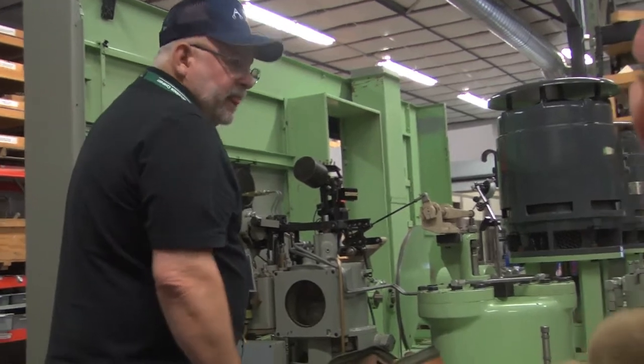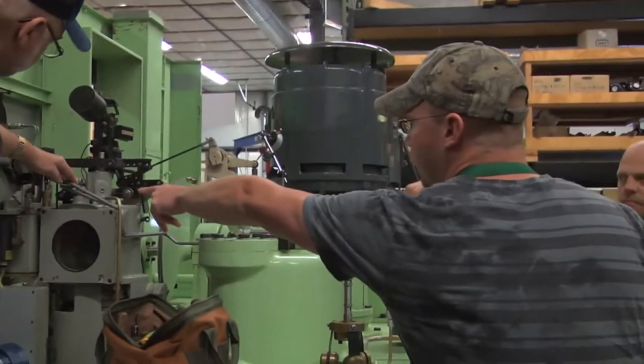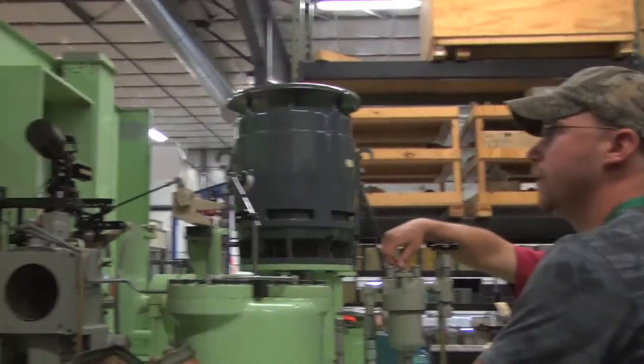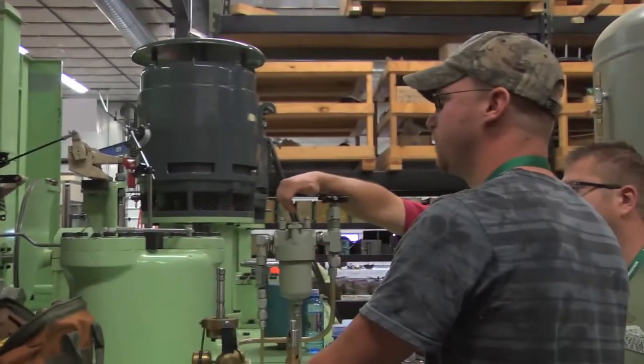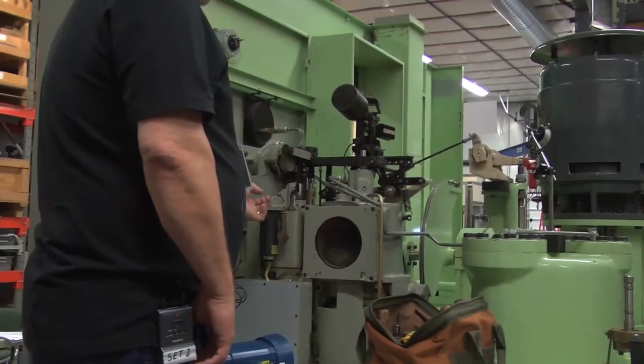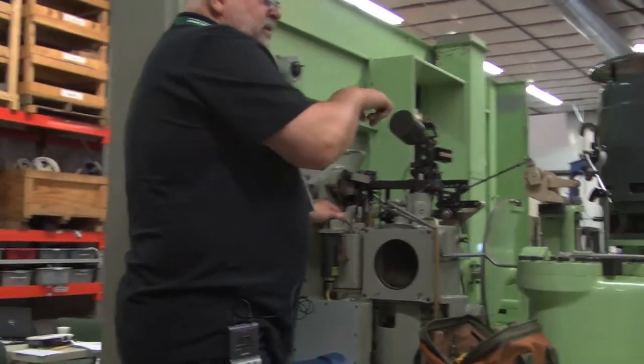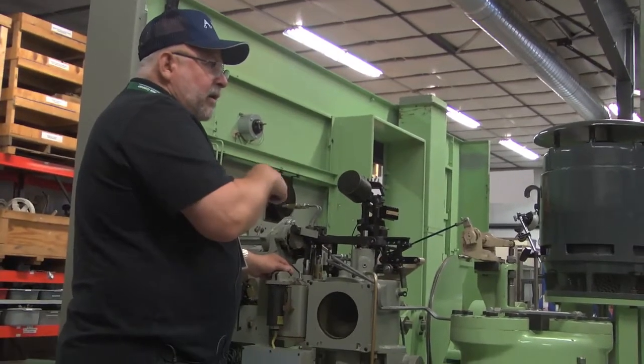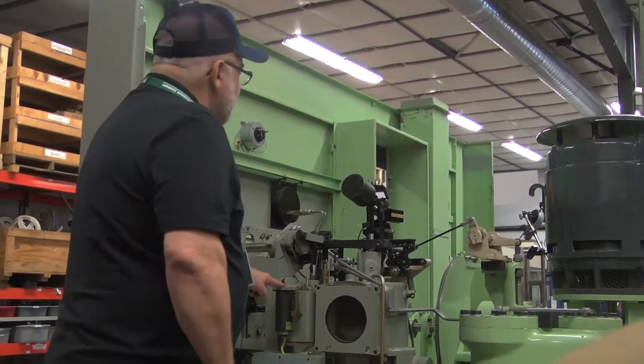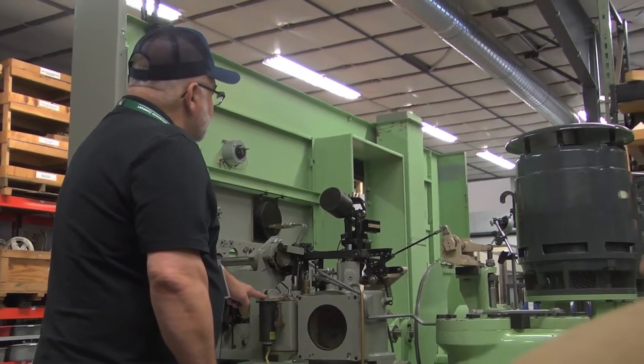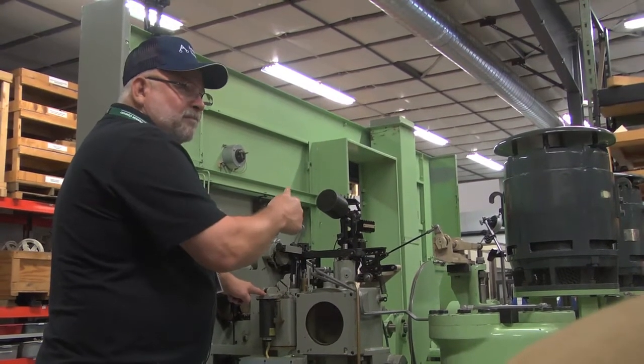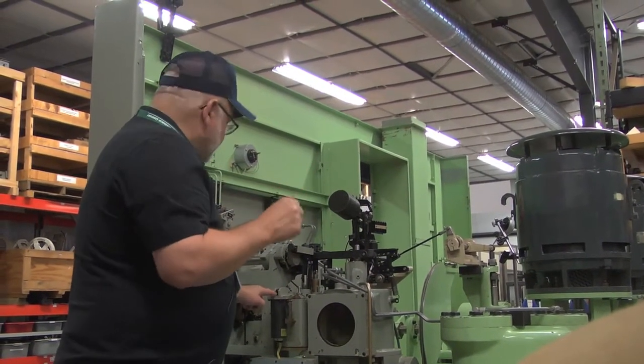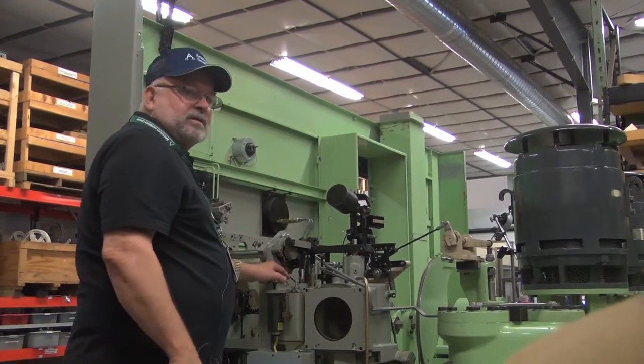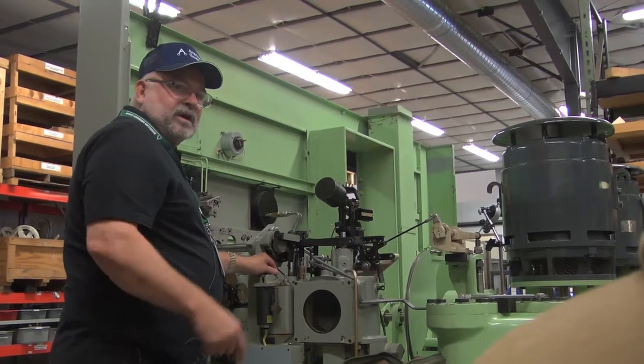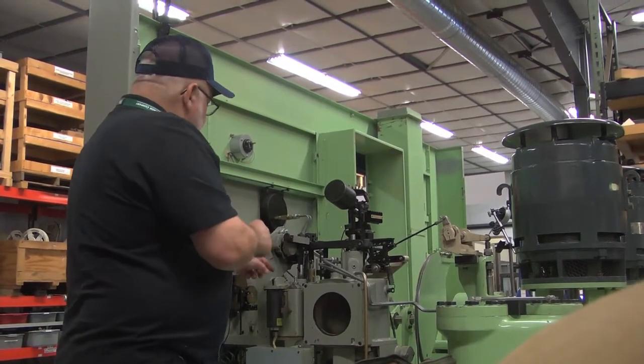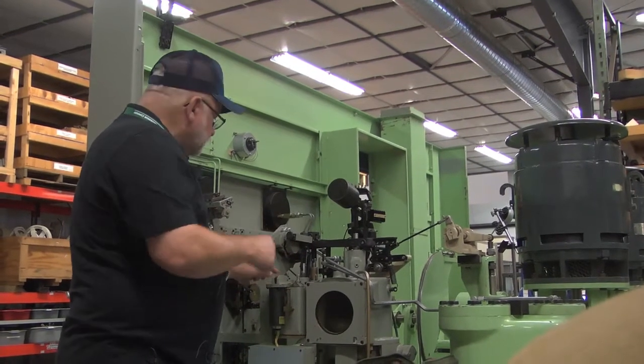I saw one time the unit was hunting and someone had forgotten to tighten the lock nut on the valve. Okay. I didn't know it till I went to adjust it. When you talk about these dash pot bypasses on a Pelton, I took it about over half a turn out. I measured this at one time. I believe it was like 3/16 or 7/64 that it pops up. So I just took a piece of key stock to preliminarily set this. When it's offline, I jumper this out and pick it up.